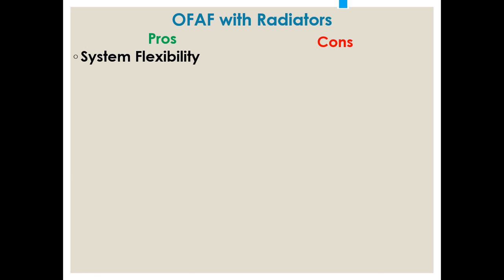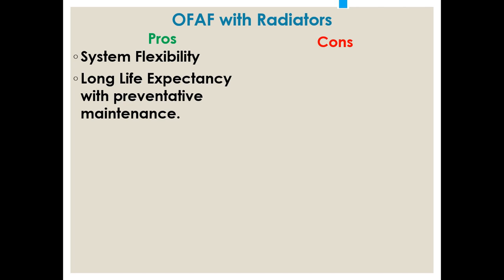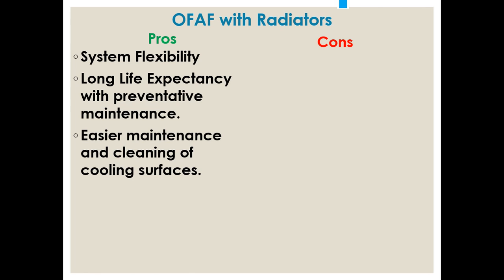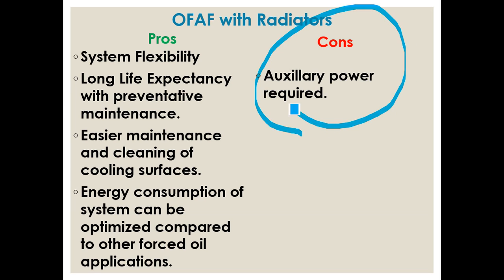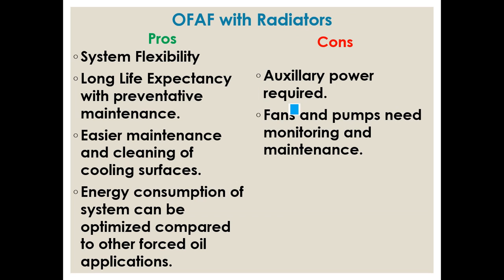System flexibility can be adjusted by using the fan off mode, but capacity will be reduced. Preventive maintenance is required - checking the fan and checking the oil pump on a regular basis. This will result in better equipment life. Maintenance and cleaning of cooling surfaces will be better because they are more exposed, and energy consumption can be optimized in forced oil applications.